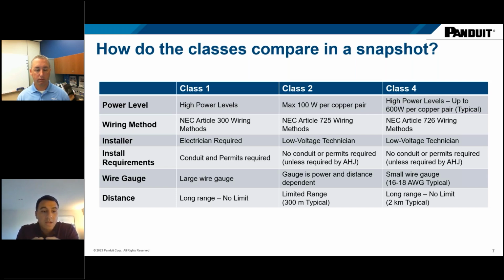In terms of wire gauge, Class 1, typically inside our buildings, we're using 10 to 12 gauge. Class 2, the gauge is very dependent on power and distance, but you'll typically see anywhere from 14 to 18 gauge. And Class 4, usually you see 16 to 18 gauge. In terms of distance, Class 1 has no limit. Class 2, very limited in range. Once you go beyond 200 to 300 meters, it becomes very inefficient. And therefore, Class 4 has no real limit on the distance. You can see systems going up to typically 2 kilometers, if not more.